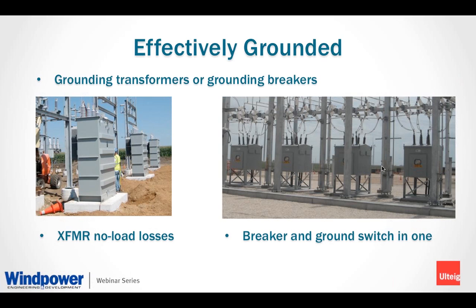Most wind farms run on a delta system. So when the feeders have some sort of issue and a fault, they'll have their substation feeder breaker protect them and turn it open. And it seems like the turbines can produce power a little bit longer, and this causes a voltage rise on the system. So a typical wind farm will either have a grounding breaker or a grounding transformer. Normally they can be located within the substation. The difference in the losses aspect is that the grounding transformer is going to have no-load losses all the time. A grounding breaker or grounding switch won't have any losses because there's no transformer there. Just another thing you can consider.